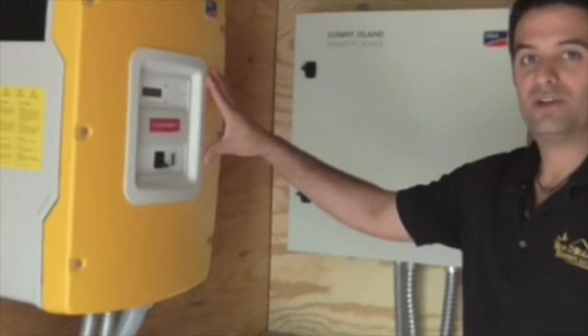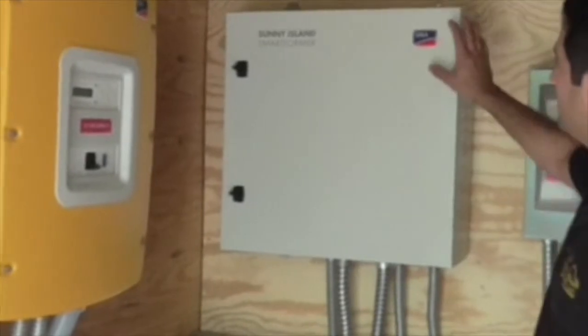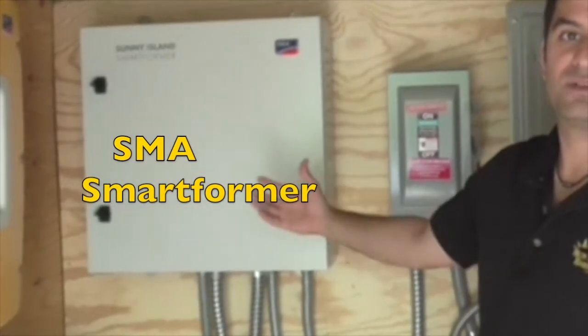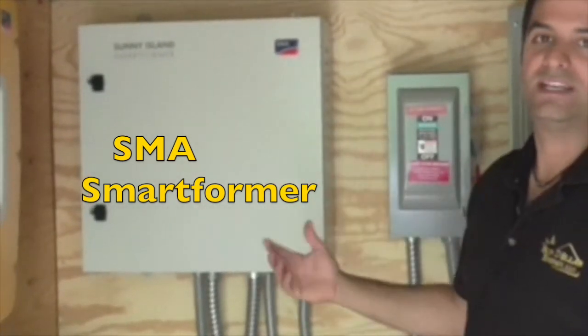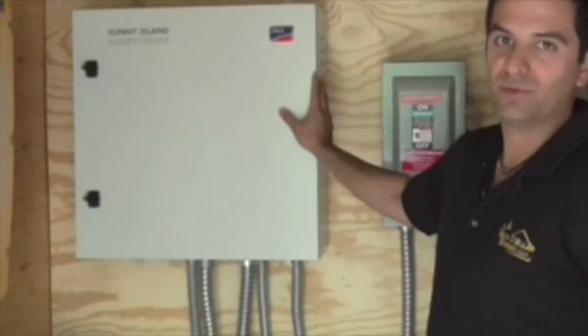The Sunny Island outputs 120 volts. We've got our tray here to the Smartformer. The Smartformer can then up the voltage to 240 volts if there is a load that needs that. In this case, the well pump needed 240 volts, so we needed the Smartformer.